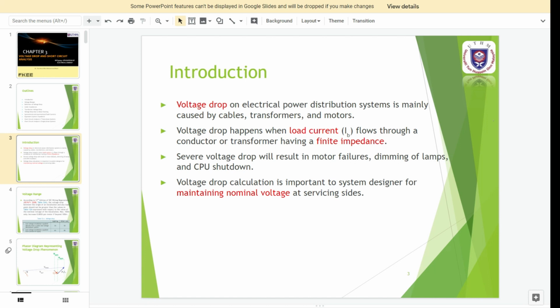Okay, introduction. Normally, voltage drop in an electrical power distribution system is mainly caused by the cables, conductors, transformers, and also motors. These voltage drops happen when the load current IB flows through a conductor or transformer having a finite impedance. Just a simple illustration of this voltage drop is like this.